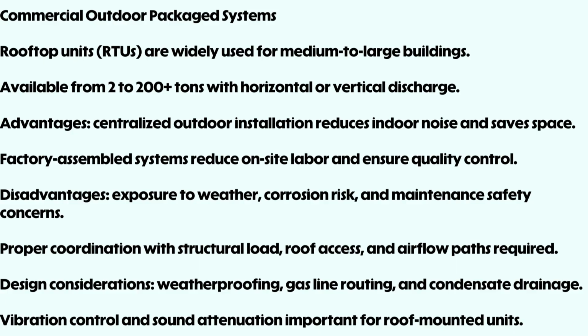Of course, there are some challenges. Outdoor exposure means potential weather damage, corrosion, and maintenance safety concerns, especially in harsh climates. That's why proper design coordination is essential, from verifying roof load capacity and planning safe access routes to ensuring clear airflow paths. Designers must also account for weatherproofing, gas piping routes, and condensate drainage to prevent roof damage. And since RTUs sit directly above occupied spaces, vibration control and sound attenuation are key to maintaining comfort below.